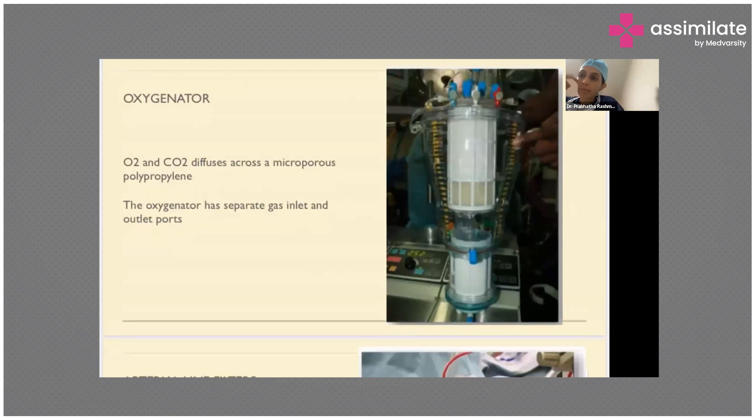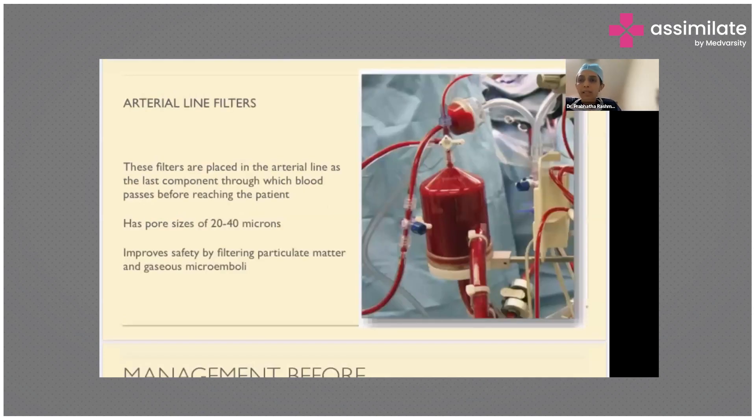The oxygenator gets its gas supply from the oxygen supply connected in the theater via one of the gas inlets. The arterial line filter is the last component blood flows through before returning to the patient. We don't want any debris, clot, or anything to enter the aortic circulation. These filters are about 20 to 40 microns in size, filtering particulate matter and even gaseous microemboli, making it safer for the patient and helping prevent embolic strokes.